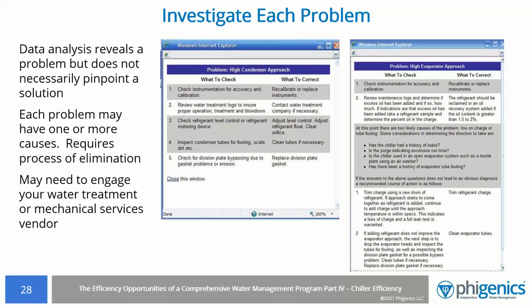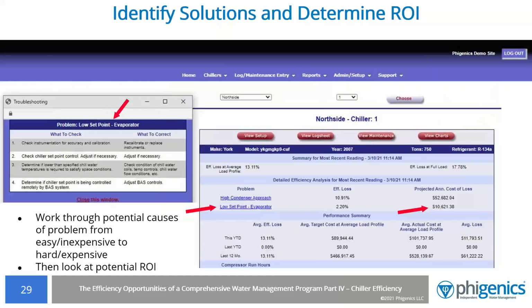So, you've identified some problems as a result of your analysis of the data. It would be too easy if that analysis directly pointed to one specific problem. Unfortunately, that is not the case. It's a process of elimination. If you are lucky, it may be just a gauge out of calibration. Sometimes it is not an easy or inexpensive fix. Other issues may be hard to confirm or expensive to repair. When you get to one of those problems, you need an idea of what the potential return on investment is.